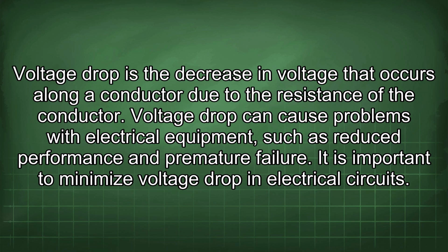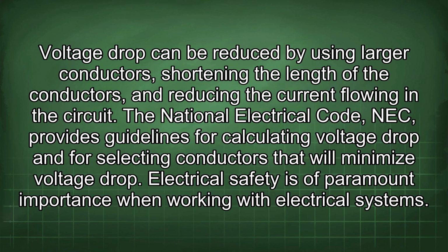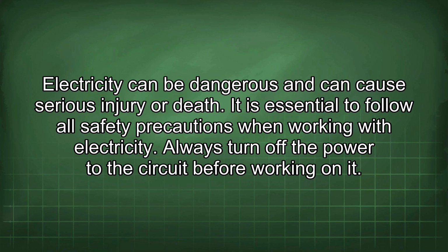Voltage drop is the decrease in voltage that occurs along a conductor due to the resistance of the conductor. Voltage drop can cause problems with electrical equipment, such as reduced performance and premature failure. It is important to minimize voltage drop in electrical circuits. Voltage drop can be reduced by using larger conductors, shortening the length of the conductors, and reducing the current flowing in the circuit. The National Electrical Code, NEC, provides guidelines for calculating voltage drop and for selecting conductors that will minimize voltage drop. Electrical safety is of paramount importance when working with electrical systems. Electricity can be dangerous and can cause serious injury or death.